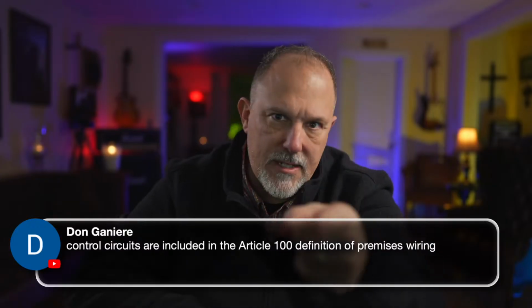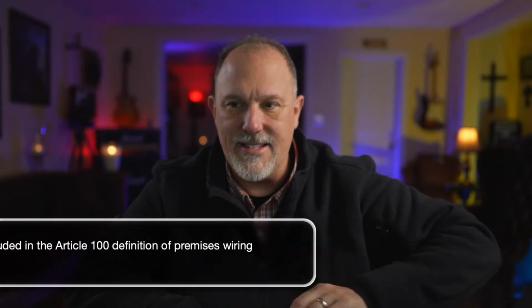Anyway, this is going to take a little bit more of a discussion, and I'll draw it out, and I'll point out the requirements. So I would go to 250. I wouldn't go to 430. I would go to 250, general requirements for bonding. I would go for bonding. And we really have to understand why those buttons don't have a place for the equipment grounding conductor. So I've got to do more homework on this one. I'm going to do some more homework.